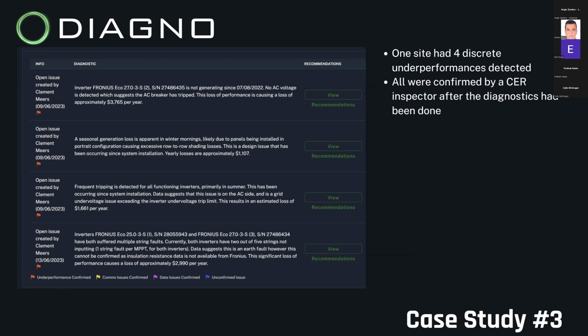We also detected frequent tripping across all inverters. And this was actually due to grid undervoltage. And so that was an intermittent fault, but we were able to detect that amongst all the other faults. And then finally, we found a bunch of string faults where strings were actually off, so not inputting into each inverter. And we were able to direct the CER inspector to those particular strings to confirm what was going on there, and indeed they were not inputting. So four overlapping issues on one system, one site. And we were able to diagnose all of them before anyone had gone to see the system, and then all four were effectively confirmed by the inspector.